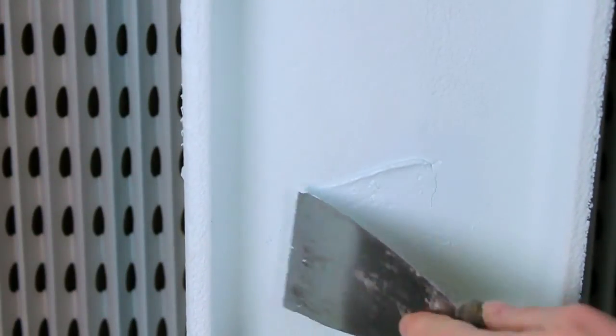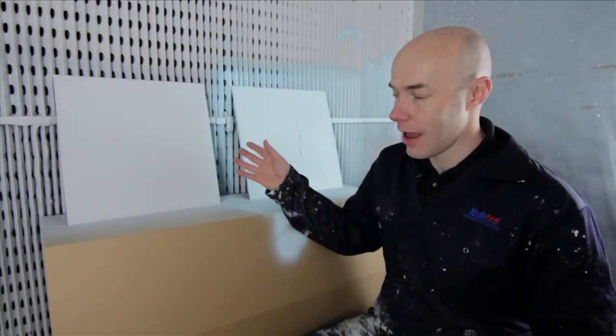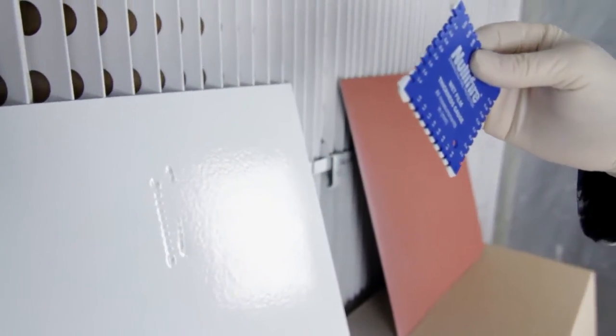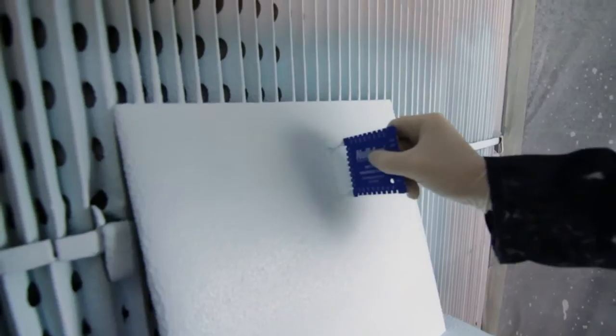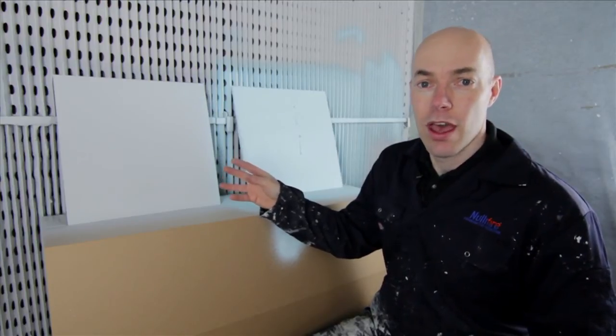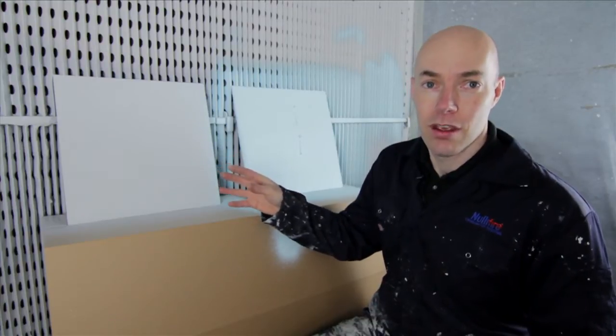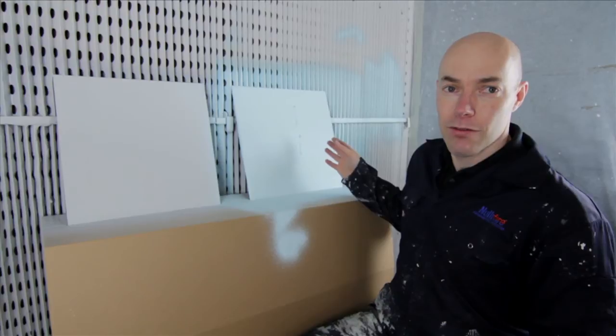This can then be given a final sanding when cured. What we've just done is applied Nullifire S707120 onto the left-hand plate to a thickness of 1.2mm, and then on the right-hand plate we've applied our new SC900 range product to a rough application of between 3.5mm and 4mm wet. The S707120 at 1.2mm wet film thickness is a typical build, but that's very much the upper limit of current water-based intumescence. In comparison, the SC900 range goes well beyond those limits, taking us up to 4mm wet film thickness.